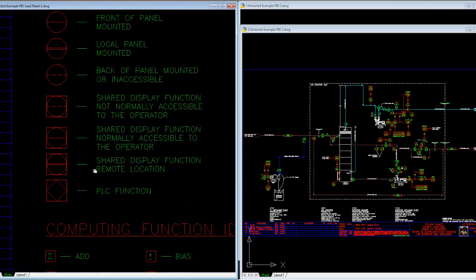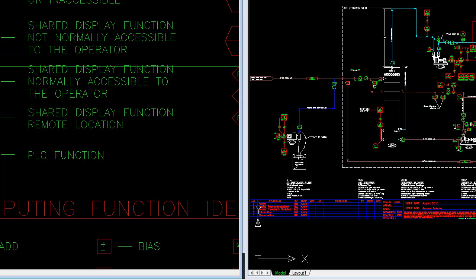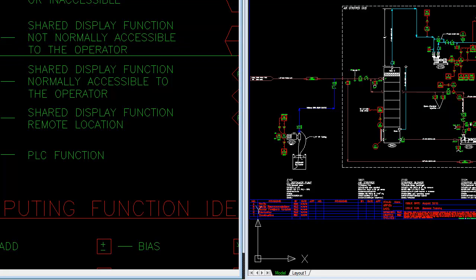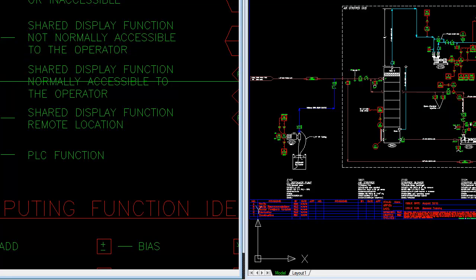In much the same way that circles with lines are used to illustrate local panel-mounted physical devices, the graphical symbology associated with controls has comparable line types. For example, a dotted line means it's not normally accessible to the operator — I like to use that for things that are maybe password-protected screens that allow you to get in and adjust PID control settings for integral rate and derivative values. You may want to change set point values or change the points at which alarms occur.